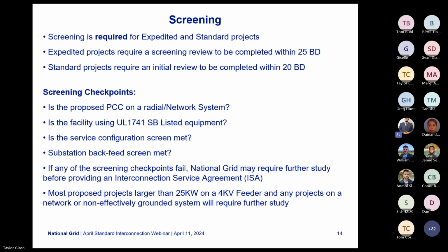Anything on a 4 kV feeder that's 25 kW or larger will be considered to go down the standard path due to the limitations on those systems. And then anything on any non-grounded or non-effectively grounded system also is considered standard regardless of the size, due to the required studies that are needed for any kind of non-effectively grounded system. Next slide, please.